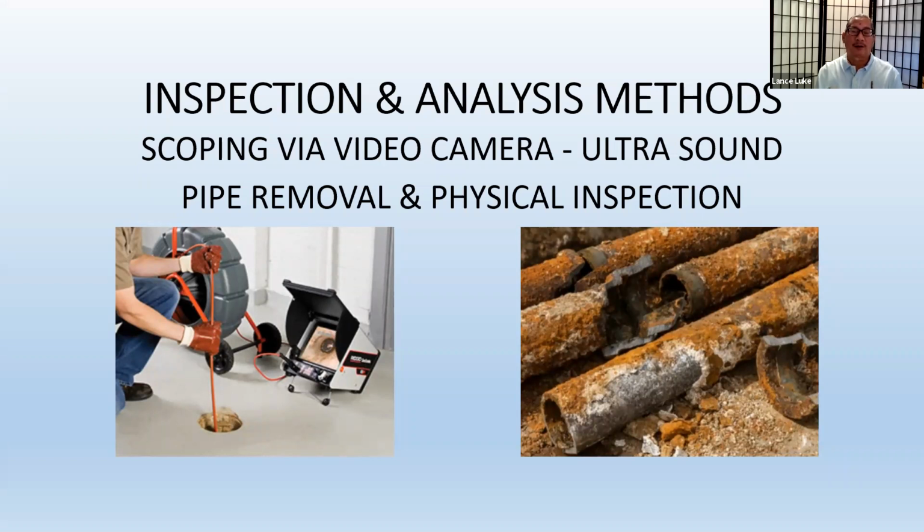The other method is an ultrasound, where it's sort of like an ultrasound for a human, but we know what the pipe size, diameter is, and the thickness of the pipe. So we extrapolate. What we do is we say the pipe thickness brand new is so many millimeters. Now, when we do the ultrasound, we can determine what the millimeter of the metal is and the percentage of degradation. And then we can kind of extrapolate and say, well, this pipe is going to last a couple more years, or you know what, it's just too far gone already. So ultrasound is another method.